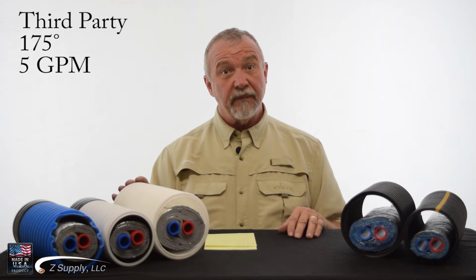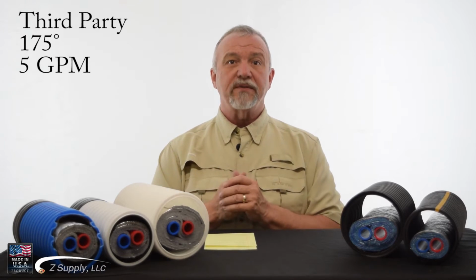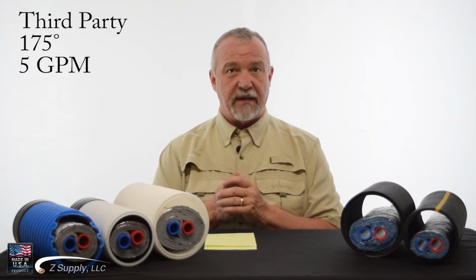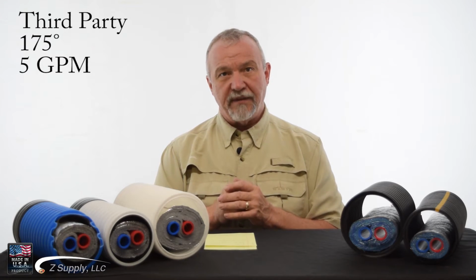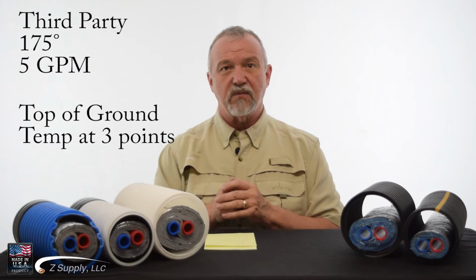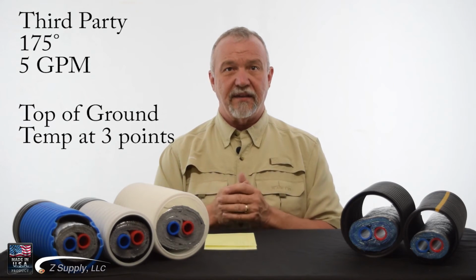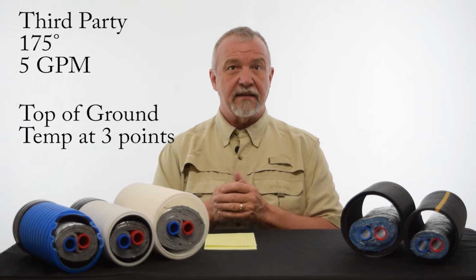Here they are. Keep in mind that these temp loss tests were conducted by a third party in as fair a manner as possible. The water temp at the boiler was 175 degrees, and the flow was a realistic 5 GPM. The tests were conducted similarly to those done by our competition. The 250-foot rolls of pipe were placed on top of the ground this winter and temp loss tested in 3 places: the supply, the return, and at the end of the 250-foot pipe.